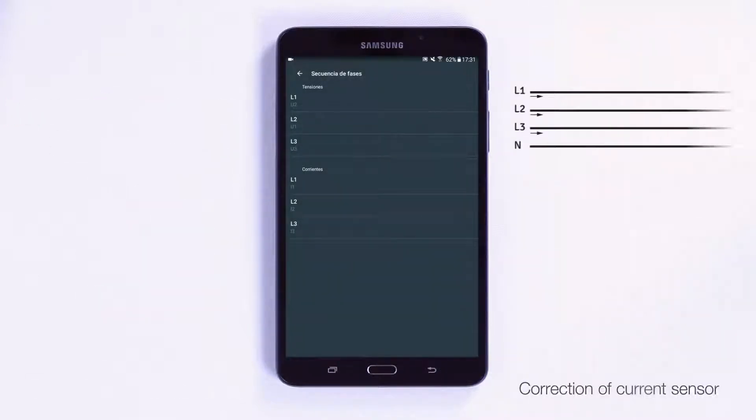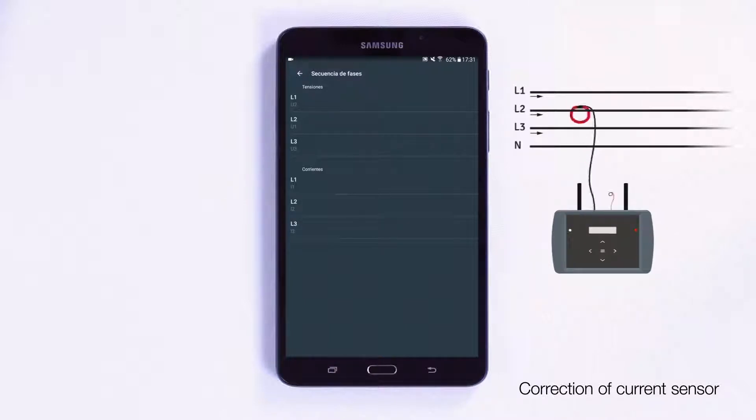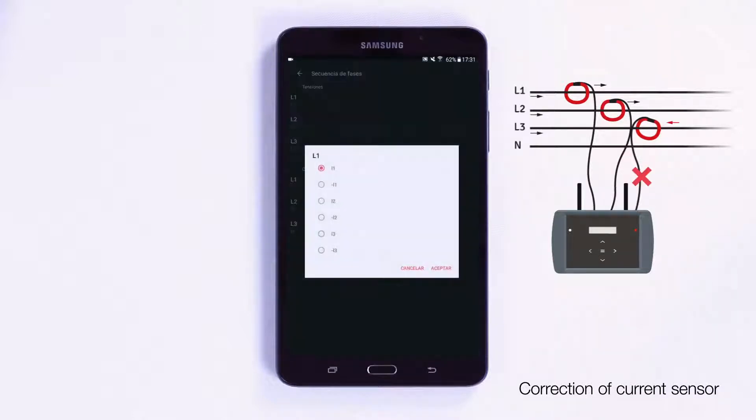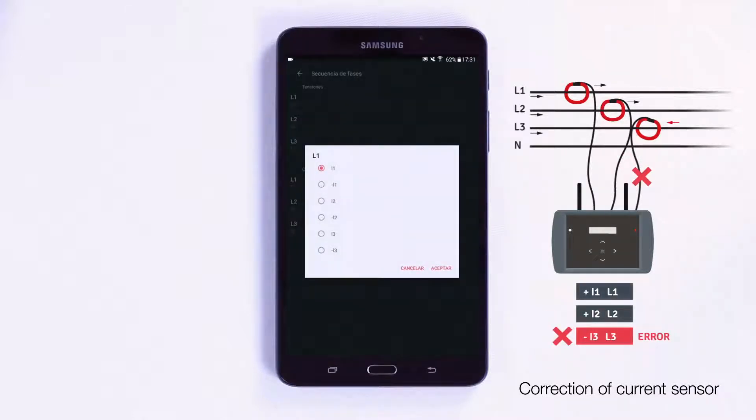Each current sensor has an arrow that indicates the direction of the current. A very common mistake is to connect a current clamp without following this direction. If this happens, the analyzer will record negative values in the specific phase, thus generating an error in the power and energy measurements.